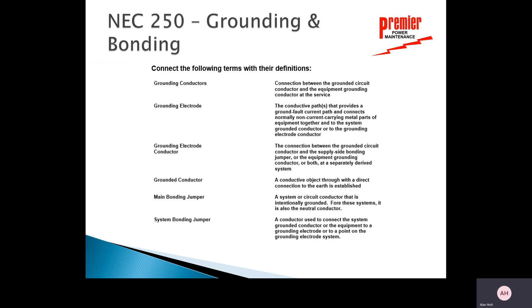Looking at the terms on the left, we need to match those up with the items on the right. For grounding conductors — what is a grounding conductor? Looking at the options, that's the conductive path that provides a ground fault current path and connects normally non-current-carrying metal parts of equipment together and to the system ground conductor or the grounding electrode conductor. Basically, it's the green wire that attaches every electrical box, every electrical compartment, and any metal casing, connecting it back to earth ground at the source.